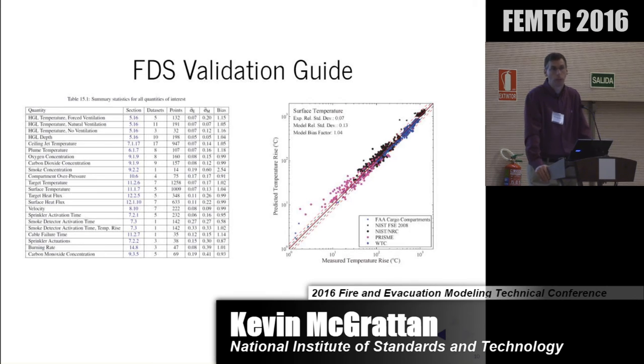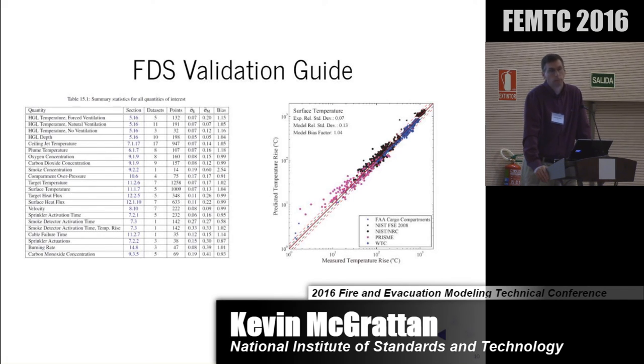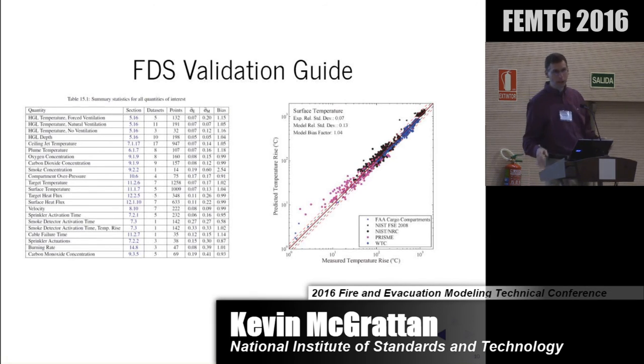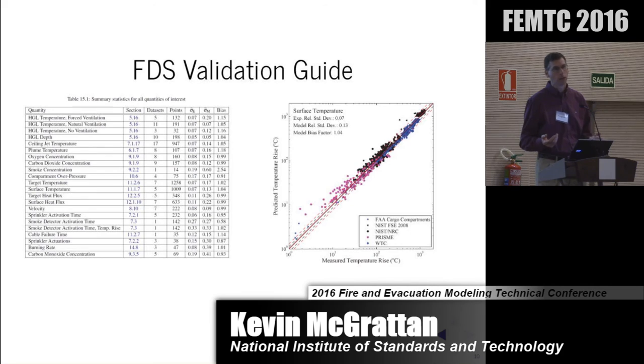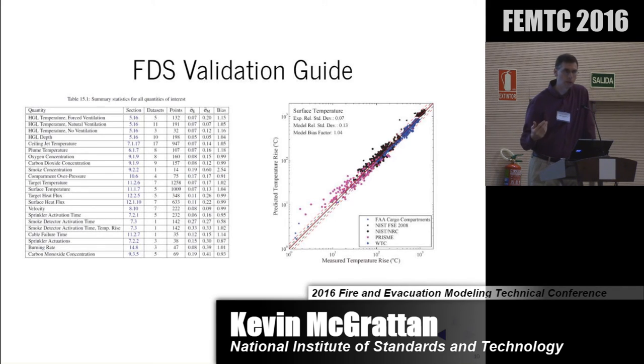That has driven us towards steady-state scenarios because that's what regulators are concerned with. The transient part is less of an issue for nuclear power plants — it's more about when the fire hits steady state, how hot is it going to be? There's no reason why we can't look at time-dependent scenarios, but it's a more difficult problem. Another comment: if you want to capture low-end temperatures, forget a thermocouple — you'd have to go to something like a thermistor. That's very hard; there's that much noise on a thermocouple at that end. Well, these experiments typically aren't ours, so beggars can't be choosers.